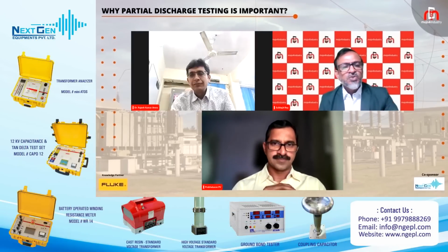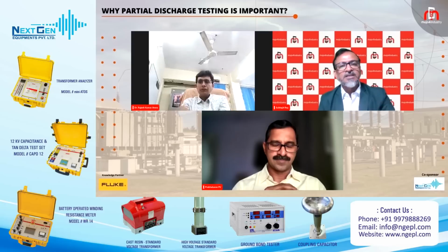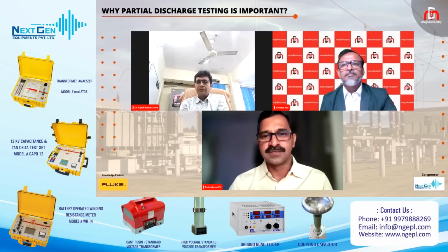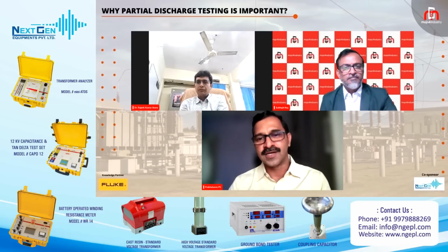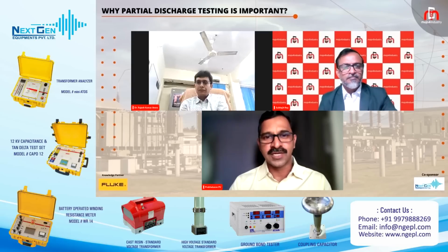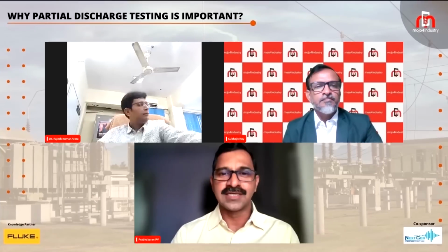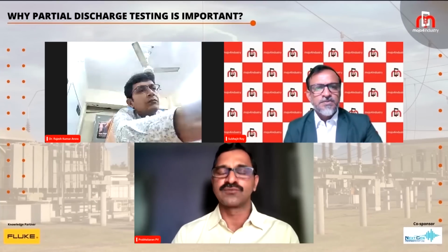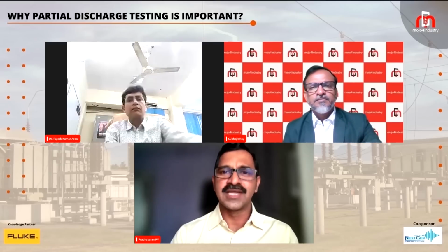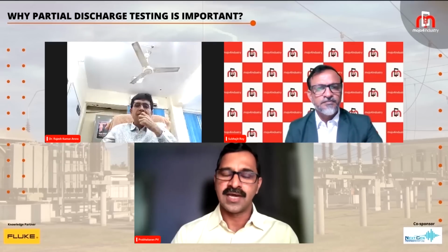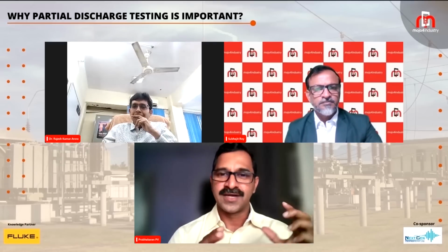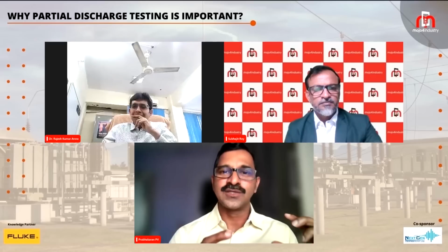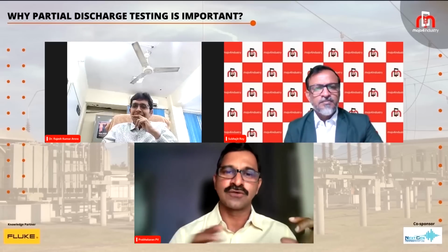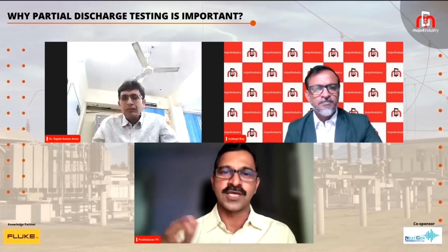Mr. Prabhakaran, what methods are available to get the right data and analyze it? The methods of partial discharge detection vary—there are high frequency methods, ultraviolet methods, sound detection methods, and the TEV, or transient earth voltage method. Most of these are electrical side, and some are online. There are difficulties in using different technologies, and each has its own pros and cons.